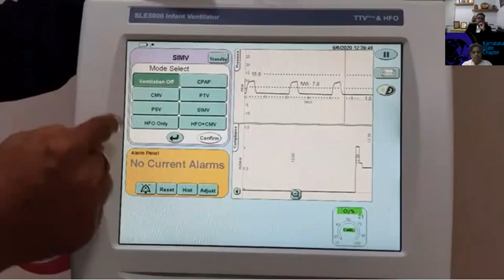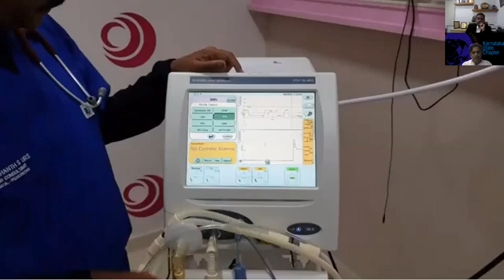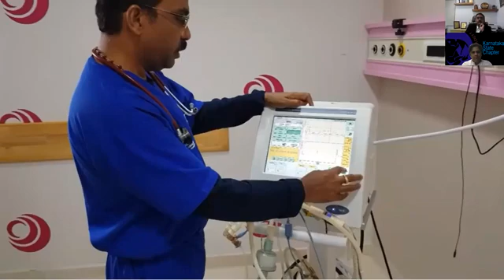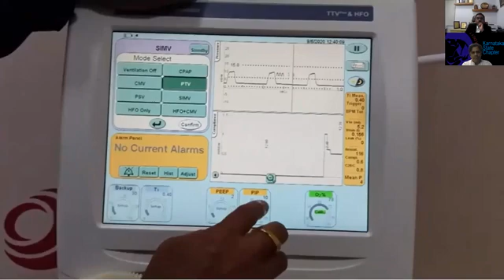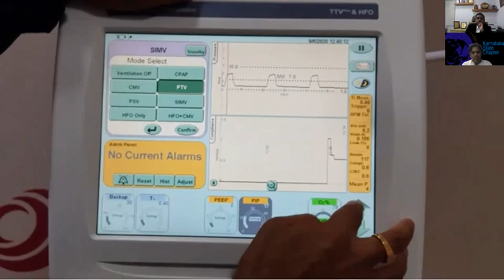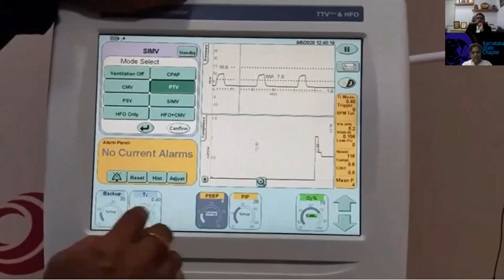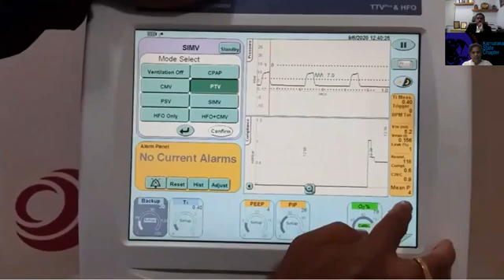Now to begin with, let us go to SIPPV, or patient triggered ventilation. As you see, I have connected this to a test lung, so it's not on a baby. First, oxygen: you can keep it at 75 or 80. Then peak inspiratory pressure, and keep it at about 26. PEEP, keep it at around 5. Inspiratory time is at 40, and backup I'm going to keep at 40.